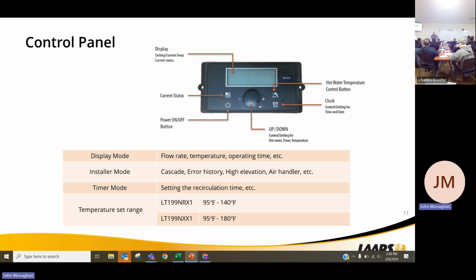So your control panel, that's what you walk in there and you don't have to scrub up. Yes. So the control and the display are going to be very similar to the FT heating, the FT boiler series. You can also get your flow rates through your display. So if it is underperforming and the customer's like, hey, I'm running out of hot water, what are you drawing? You come to find out that they have one shower head in there that's capable of 7.5 gallons a minute. You're able to see that from that display. We're able to see what the flow is going through that boiler. Basically, it's a magnetic Hall effect sensor.